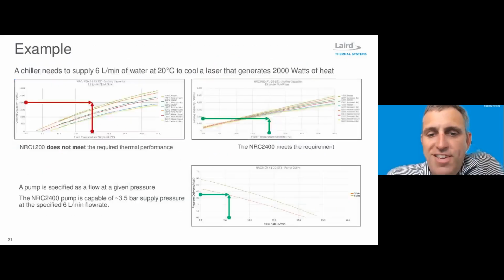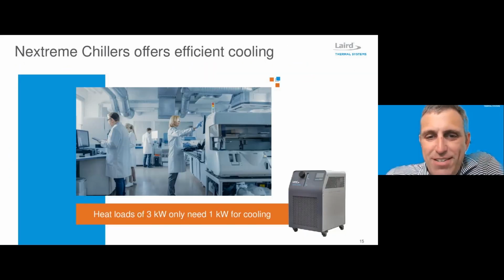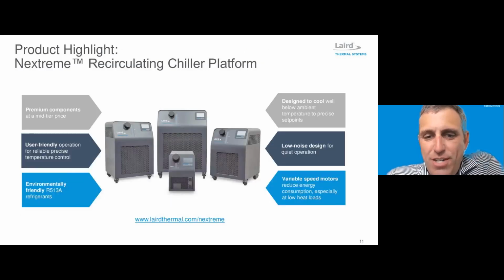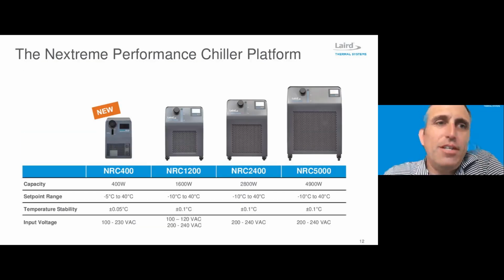Okay, so when we talk temperature range, I'm going to go back to there's two things that we need to keep in mind. One is the temperature. I assume this is probably the set point range. So set point range of the product is -5 degrees C to 40 degrees C. Now, we can follow up either with what a performance curve looks like for a thermoelectric chiller. These are based on temperature differentials. So it depends on where you're coming from. If you're a refrigeration person, it seems more complicated. If you're a thermoelectric person, it seems easier.